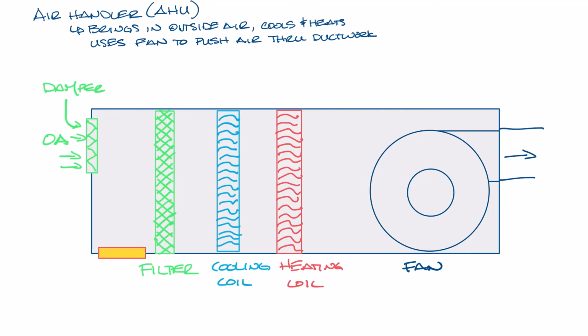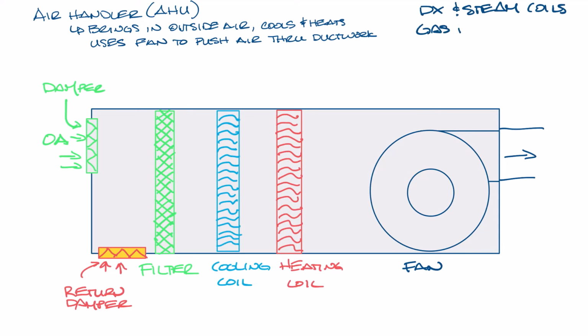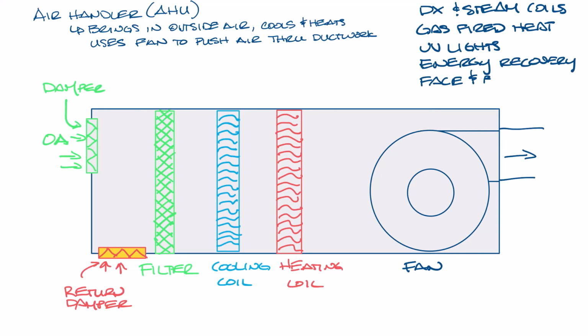An air handler will probably also have a return air damper. Often the return air is mixed with the outside air and recirculated through the space. There's a lot of other components that could go into an air handler. I referred to hot water and cold water coils, but you can also have DX coils, steam coils, or gas-fired reheat. You can have UV lights and energy recovery wheels. You might have face and bypass and humidifiers, and you'll probably have access doors, and there are a ton of other options that we'll cover in future videos. So this is our basic air handler.